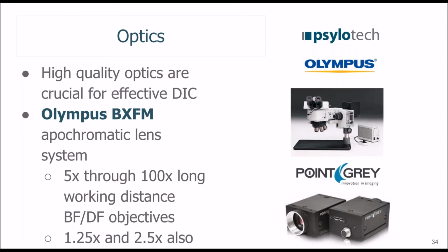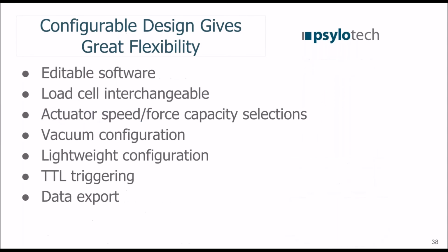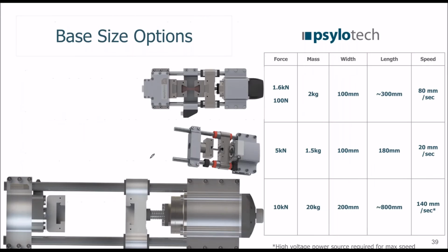We find that with the optical case for DIC, you get about 80% of the benefit and a lot less effort in setting up the test. So we recommend optical, but the system can be vacuum rated, and we have a specific system that is, let's see if I can find it here.